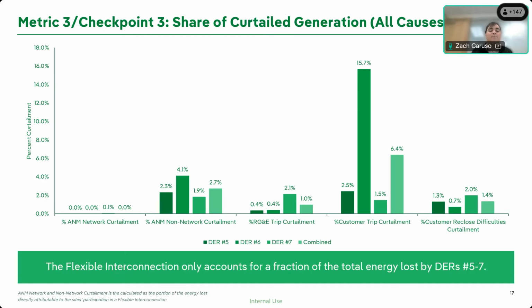the practical considerations of operating these sites. But to put that in context, those losses are on par or even less than the general loss of generation from outages, both utility and customer outages, and equipment failure and stuff like that. So it's not out of the realm of reasonableness that even for these sites, which are our first sites and where we're getting our feet wet with how we operate them and the various challenges that come with that, and making those things more streamlined, the amount of curtailment is manageable when all things are considered.